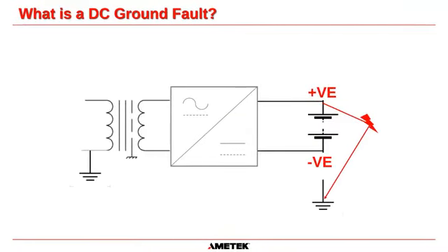Well, let's just do it on this slide. So you've got to remember that on any system, the electrical code says that the neutral point must be connected to ground at one point and one point only, and it's usually at the earliest point in the system that connects from either a transformer on a pole outside your house or from your MCC. So your MCC will probably have the neutral connected to ground, or the transformer before your MCC will have a neutral connected to ground. So my point is that the neutral will be connected to ground.